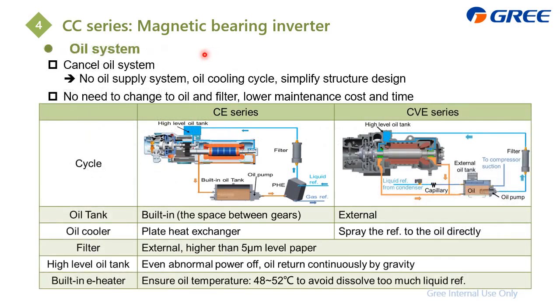As for the oil system, just like what I introduced, as the shaft and the bearing have no contact during operation, there is no need for the oil system. As we don't need it, we can also cancel the oil cooling system, which can definitely simplify the structure, and there is also no need for the oil filter. This can lower the maintenance cost and time.